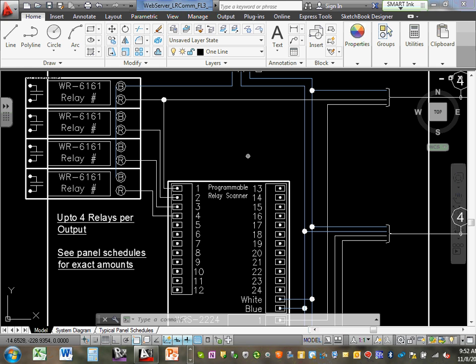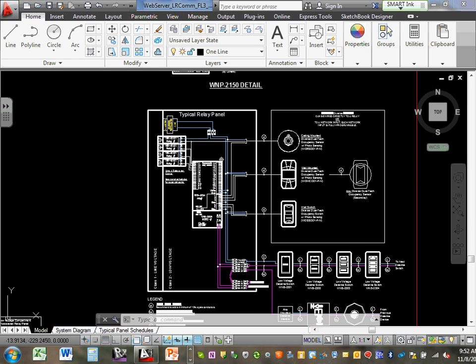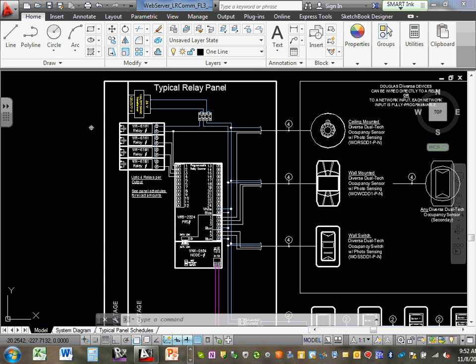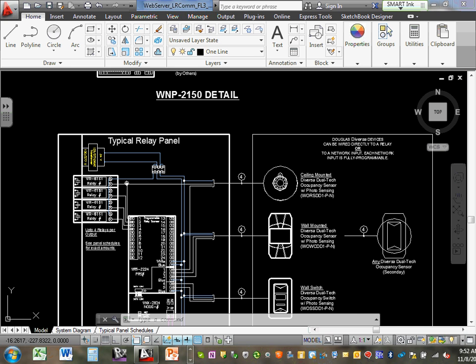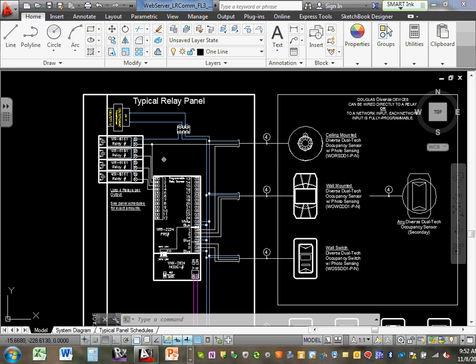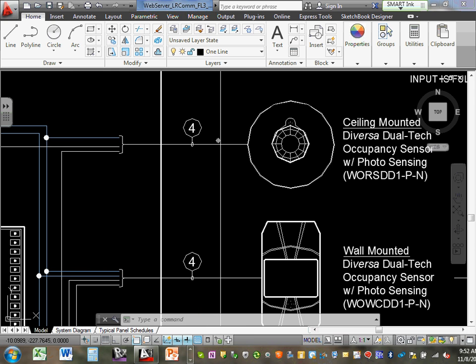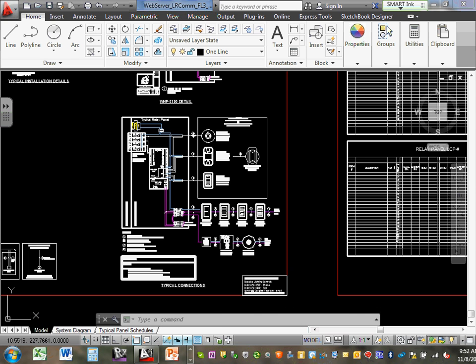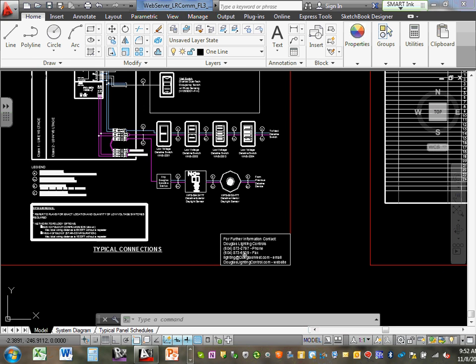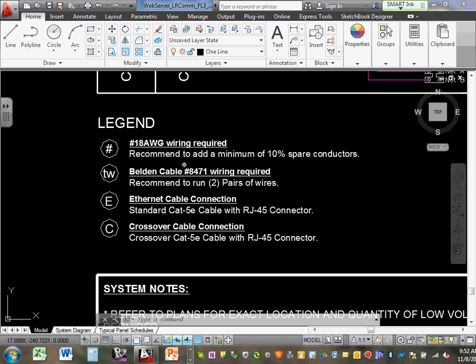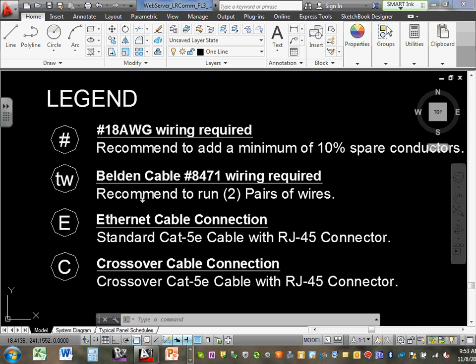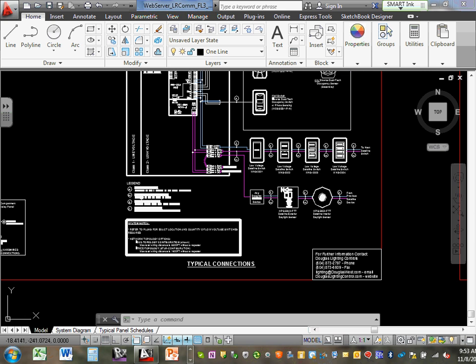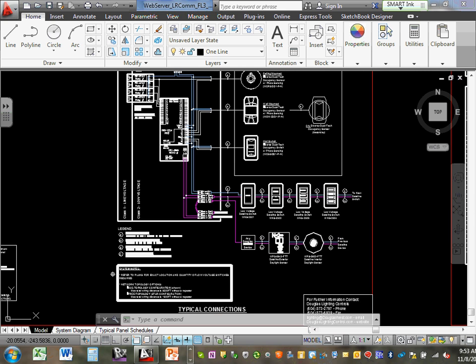What I really need to do is land the circuit on the line voltage side of the relay. I need to land the proper circuit to it. So I can't program the hardwiring, right? Once it's in, I can program it, but I have to know what circuit's being tied where. So when we look at the panel schedule, we'll show you why that's so important to us. So we break that down. This number is going to tell you the number of conductors. There is a key down in the lower right. I think that's it. Nope, right in here. There we go. So this key is going to tell you what that wire is, whether it's a Belden cable, an Ethernet cable, a crossover cable, or just a simple 18-2. So it breaks that all down for you and tells you how things hang.